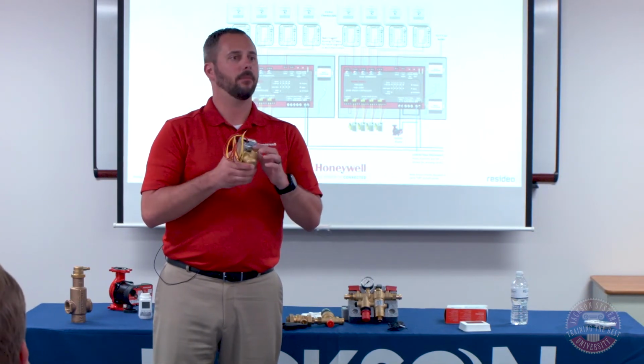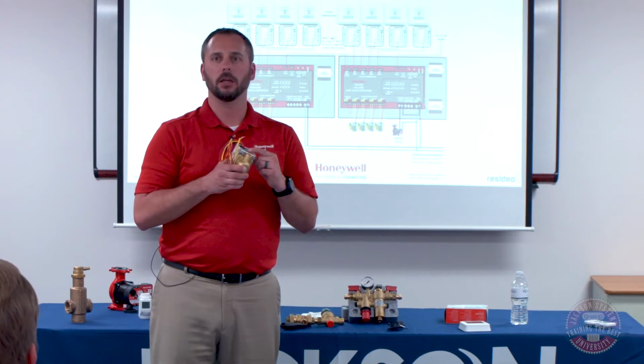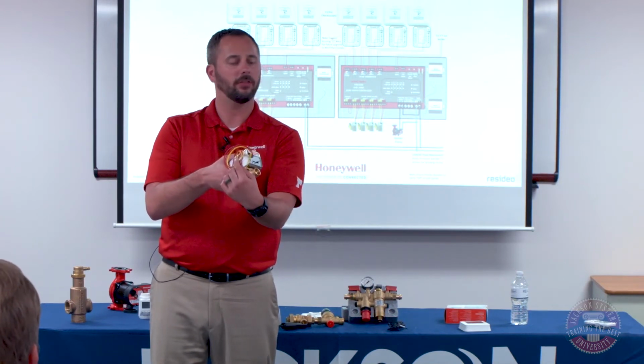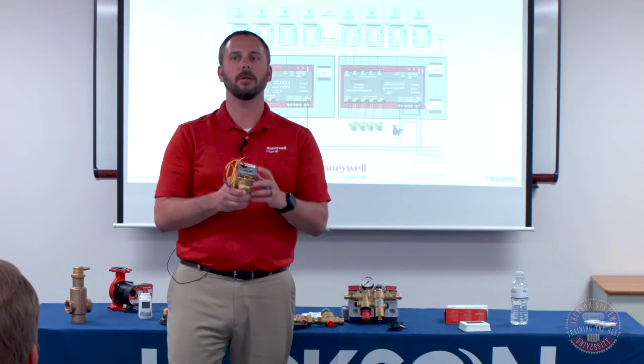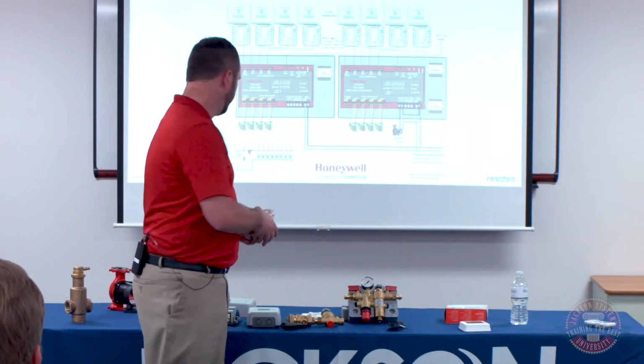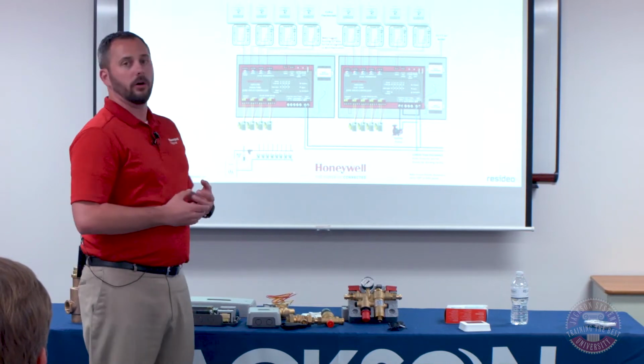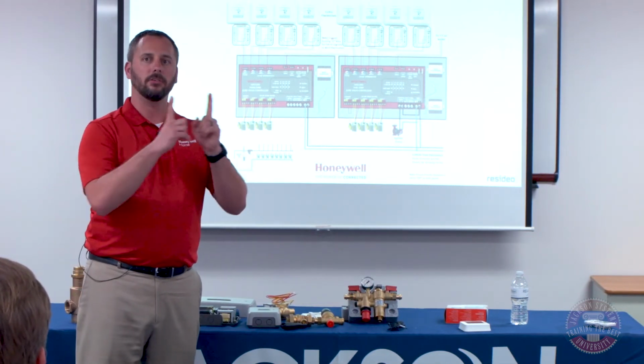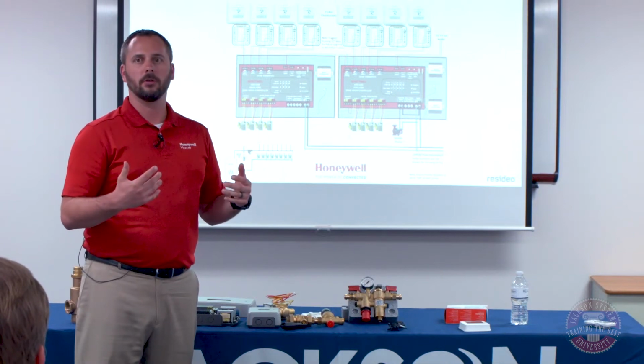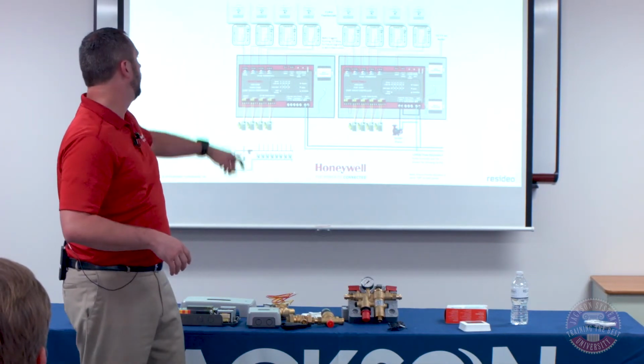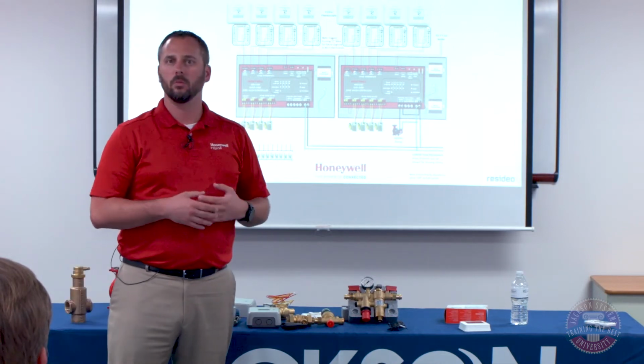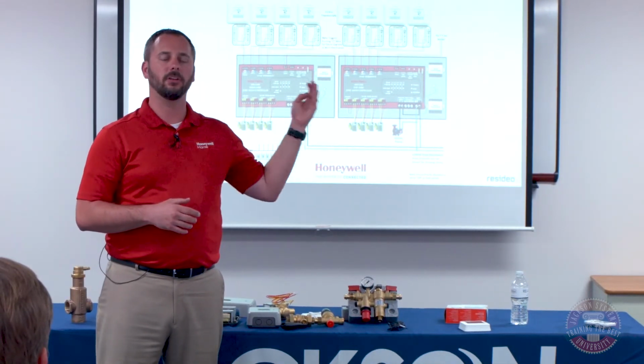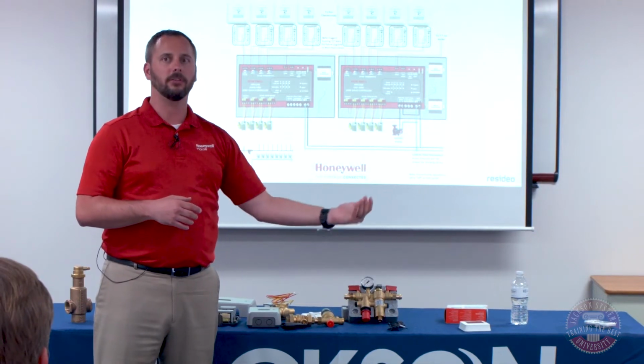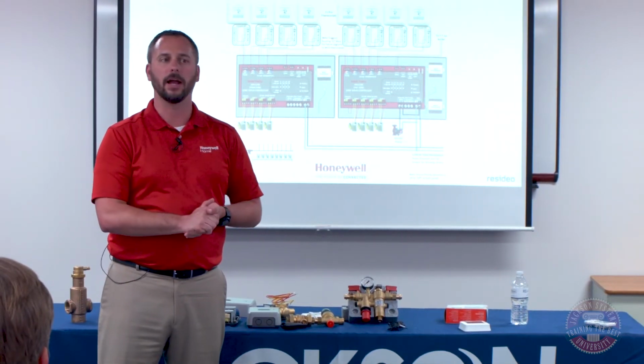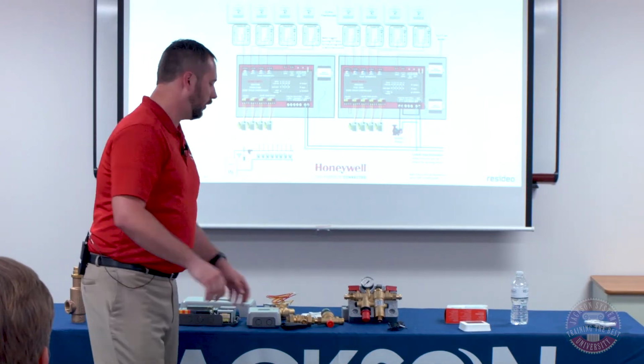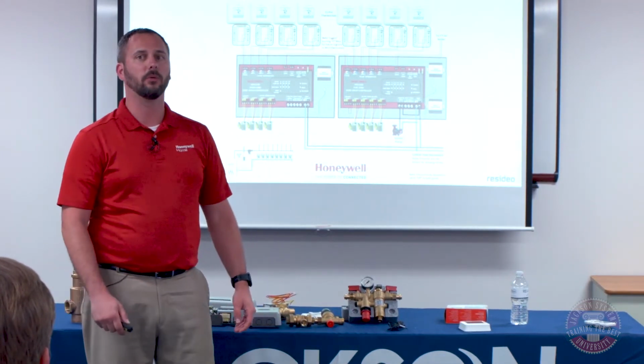One fact about that is it's only done electronically. If you manually open this valve, it does nothing to the end switch. So it has to be powered with 24 volts to get the end switch to close. Our board doesn't tell the boiler to come on until it sees a contact closure across the end switch. So we can trick the board in this example by putting a jumper between 3 and 4, which is our end switch closure. Basically, when it sees a contact closure across the thermostat, it sees that the end switch is closed and immediately tells the boiler to fire. You can also do that same trick if you have 2 wire zone valves with no end switches.